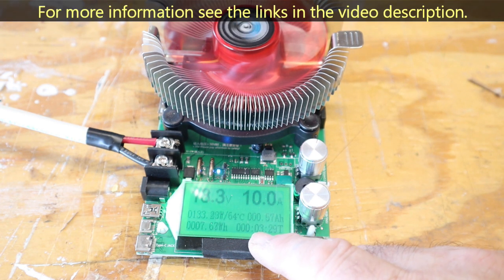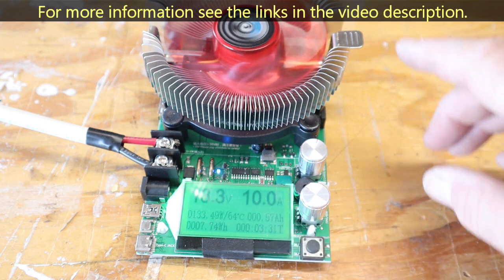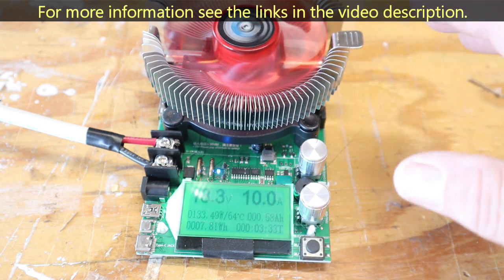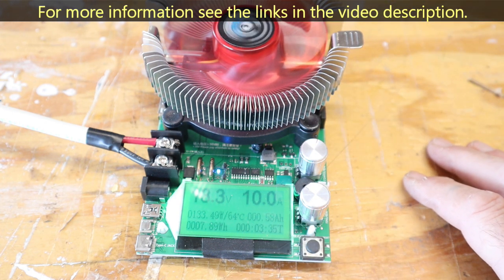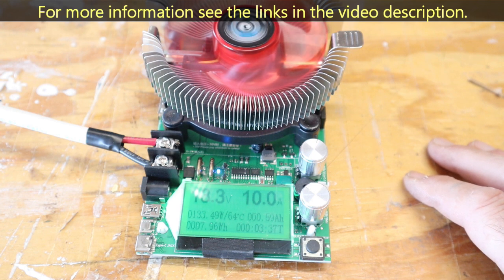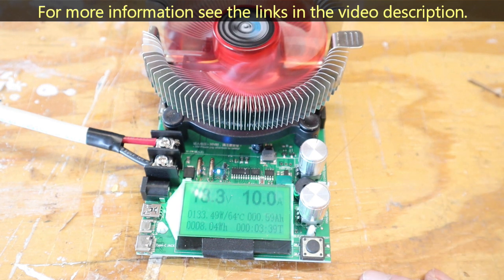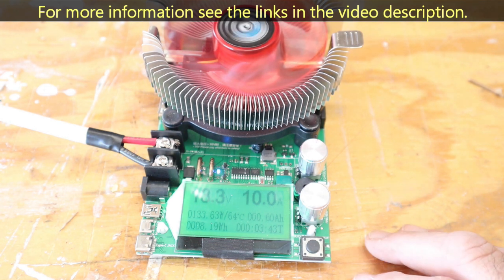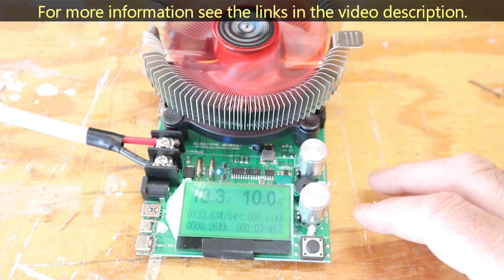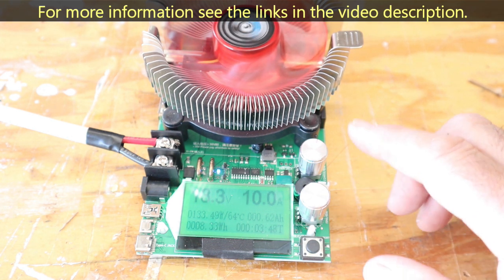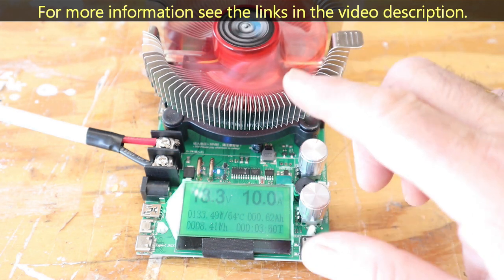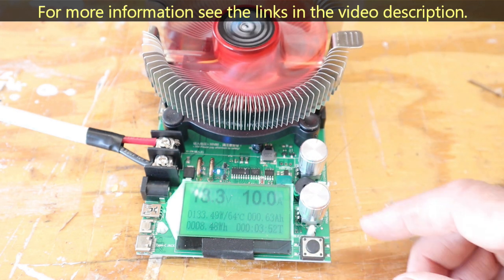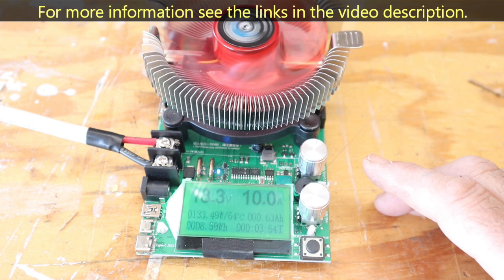I got it set at 10 amps because since it's a 280 amp hour battery, it should take about 28 hours to discharge completely, and discharging at a slow rate should give me a more accurate reading. All this is really doing is dissipating all the power and energy in the battery as heat, and that's why you see this fan spinning, dissipating the heat off the heatsink.